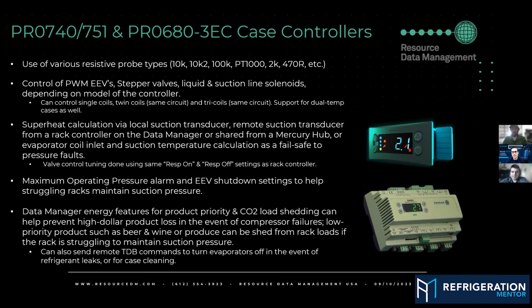How often do you see stuff like that being used? Product priority is used a lot. It's especially used in CO2. I've seen it a lot in cascade sites, because if you lose your medium temp group, you're going to lose your low temp group. And then you might want to write a little custom thing where you start staging priority for your medium temp first. So you get your medium temp running, get that all good, and then you start running your low temp. You don't want to start prioritizing your low temp and running that, and then your medium temp's not running.